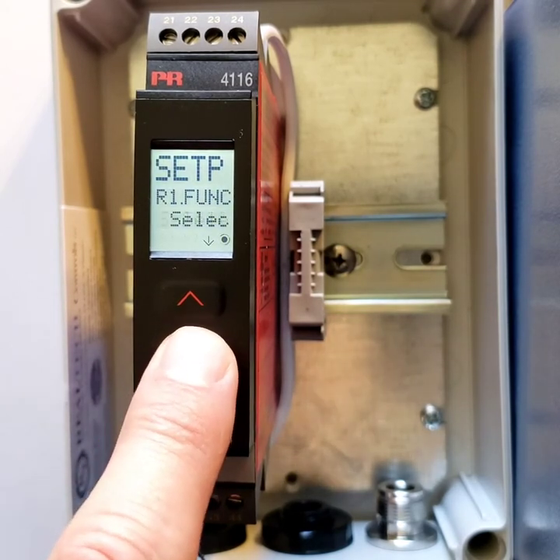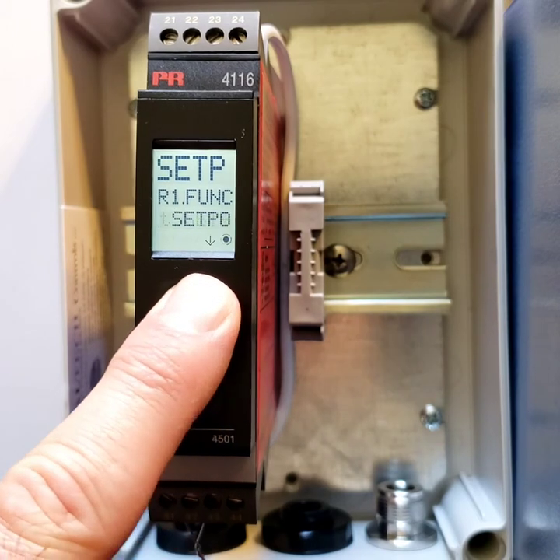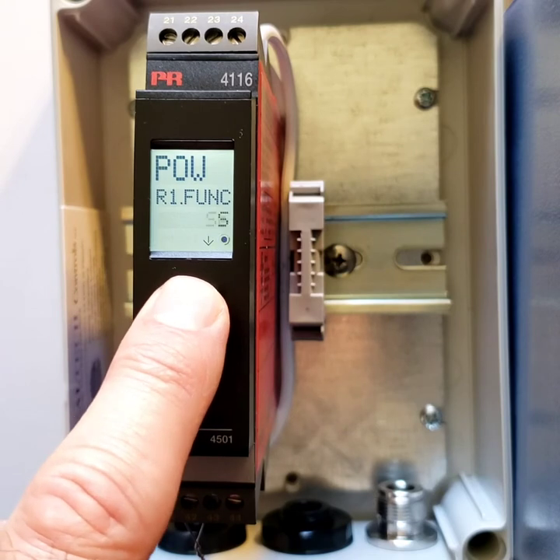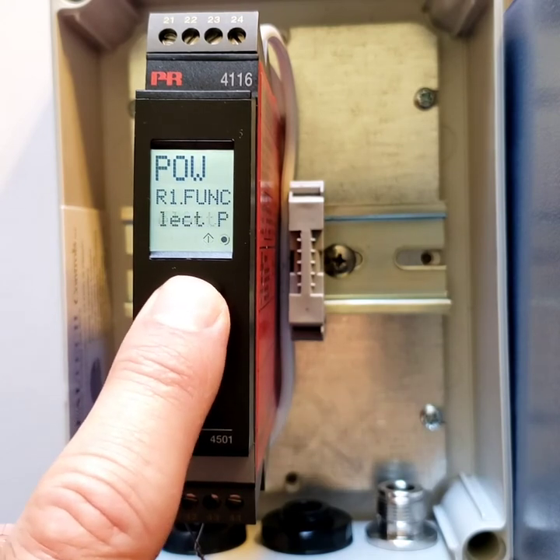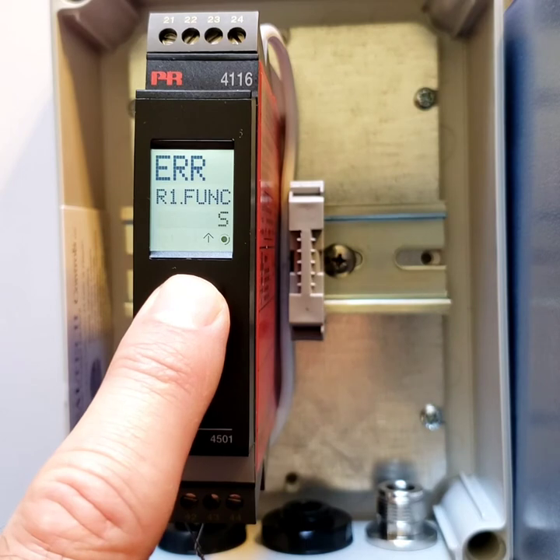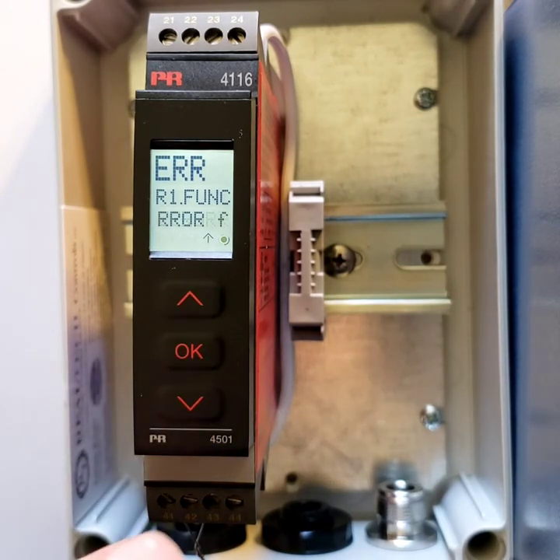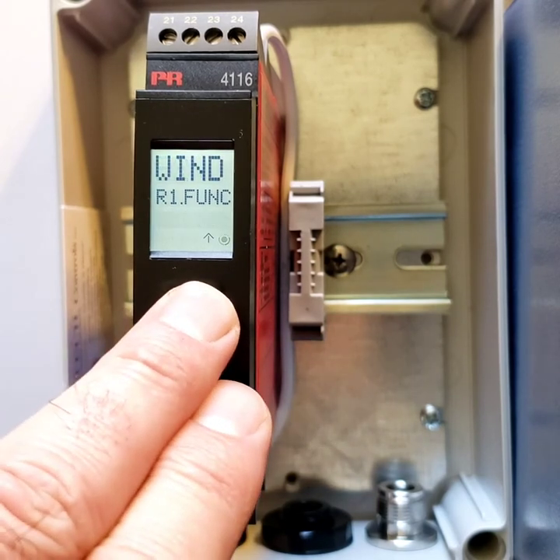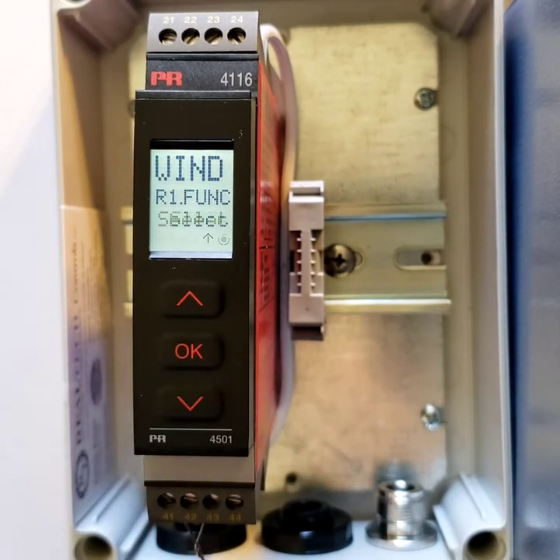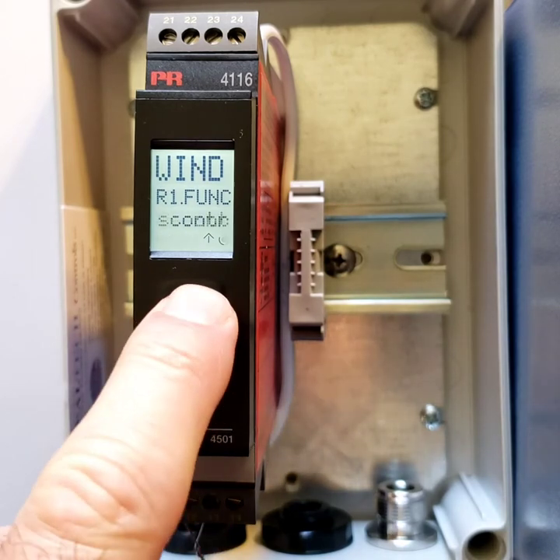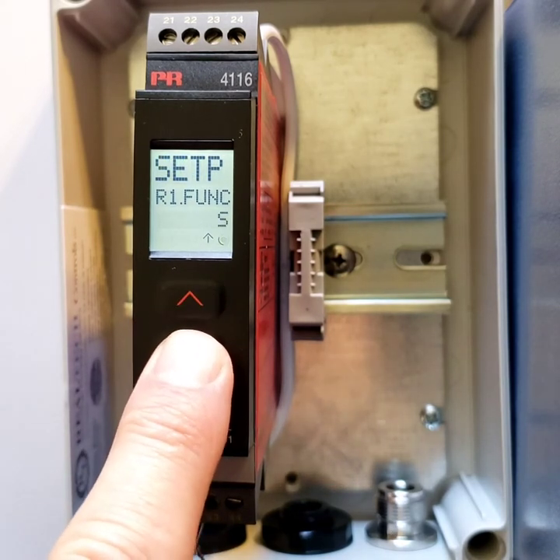Our relay function is at the moment set to set point. We also have off, so the relay will not function. Power, so the relay will function when power is applied to the unit. Or error — if there is a signal break, the unit will activate the relay if there is something wrong with the signal. Or a window function which keeps it open or closed between two values; this is useful for a tank fill or tank empty operation for basic control. We will leave it as set point.